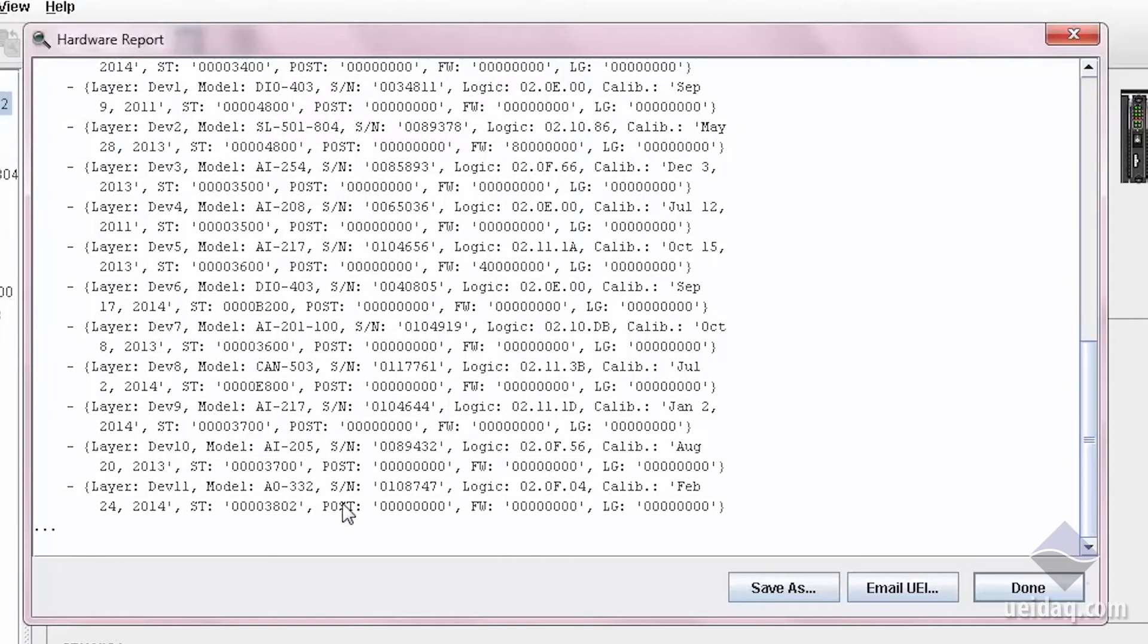And information about every single I.O. board in the system. Status, type, logic level, this is the logic that's on the FPGA on each I.O. board. And it's an incredibly helpful diagnostic tool. It gives us a snapshot of everything all at once.